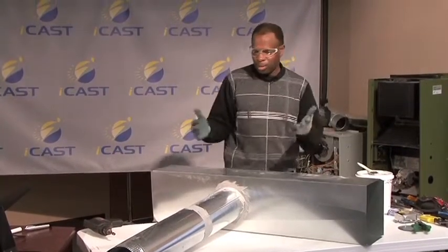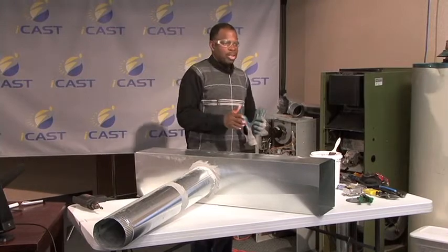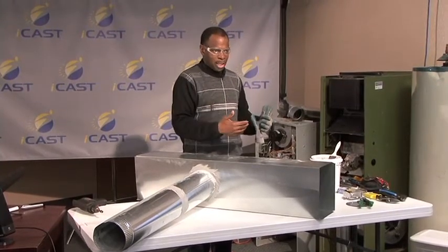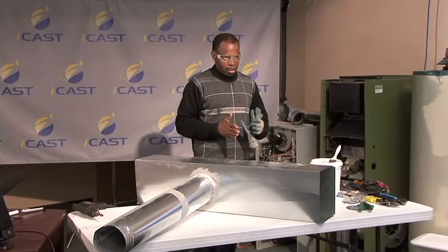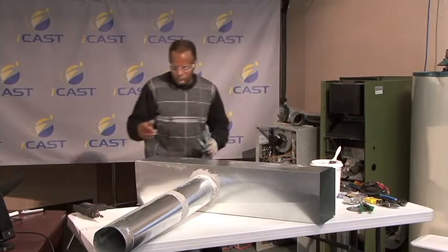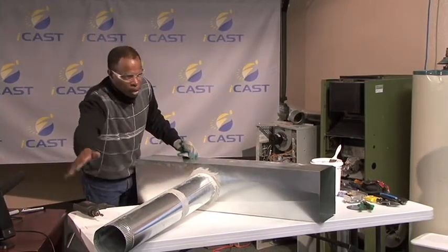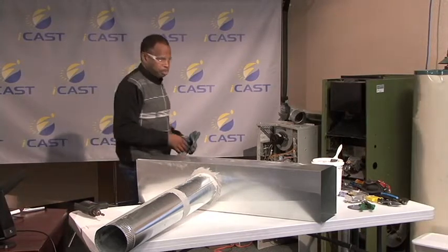Okay, and that's what the return duct will look like. If you wanted it in this room right here and it was hanging up, this is what we do. And it'll be longer, and then you'll have a register at the end. You'd have a 6-inch register at the end. You got to make sure that you get these crimps going towards the airflow. If you turn it back the other way, then you're going to get leaks. And then you'll get some whistling sound too. So you want the crimps, the air is coming in here, all my crimps were going out toward the supply. That's what you want.